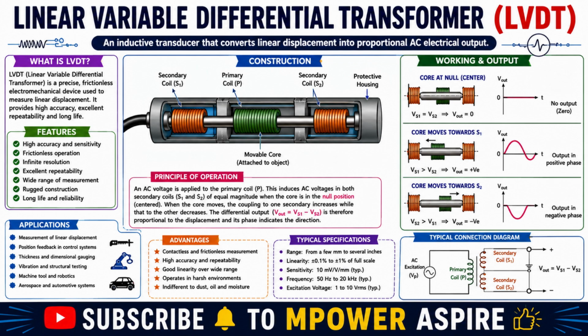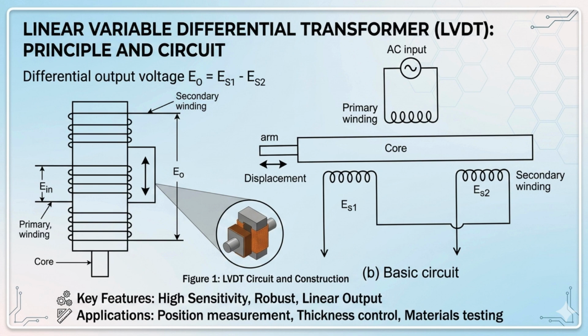Let's get started. The LVDT is the most widely used inductive transducer to translate linear motion into electrical signals. LVDT is the Linear Variable Differential Transformer, consisting of a single primary winding P and two secondary windings S1 and S2 wound around a non-magnetic and insulating material. The secondary windings S1 and S2 have an equal number of turns and are identically placed on either side of the primary winding. A movable soft iron core is placed inside the former.